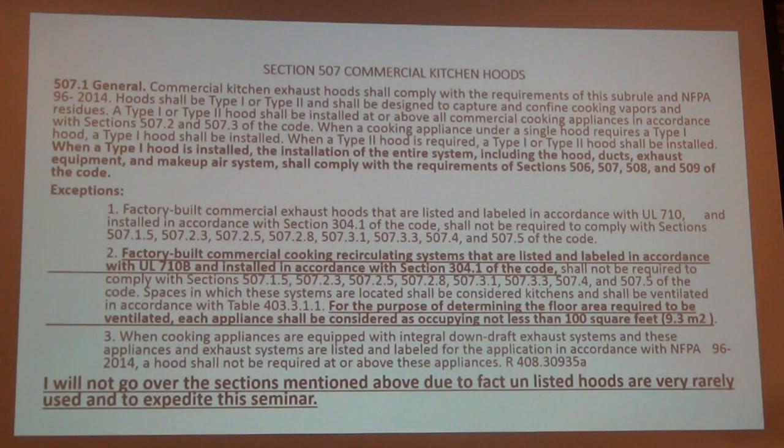Manual N. So you still need that calculation, because I had one where I made them put a mini split in because they didn't have enough air conditioning in the kitchen. They provided the heat load calculation and they couldn't meet it. That's what I'm talking about. They have to supply a Manual N calculation, not just showing the loads for the appliances, but the whole kitchen itself, to see if the air conditioning can handle it.